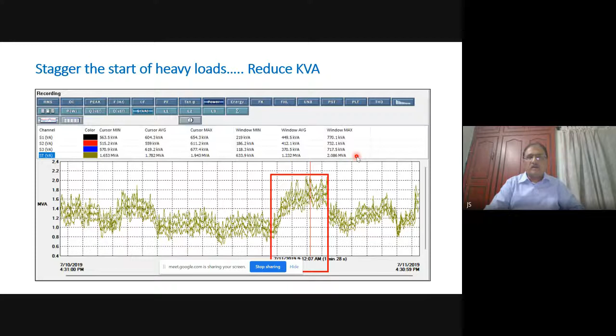Now, I also have another case, again a 24-hour data window, where we notice that at 7:20 a.m. when they started a chiller, which is the biggest load in a child hospital in Chennai, there is a spike, there is a peak KVA. For example, here the average for that one full day was 288 KVA, whereas the maximum registered at that time, as you can see the spike here, was 532 KVA. So you are paying in Tamil Nadu, for example, 375 rupees or 350 rupees per KVA as the demand charges.